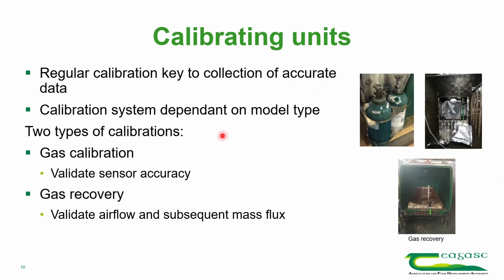The two calibrations: the first is looking at gas calibration, to validate the sensor accuracy. Basically what we do is put in a known concentration of methane, carbon dioxide, and a balancing gas, pass them into the unit, and make sure the sensors are accurately picking up those concentrations of gases.